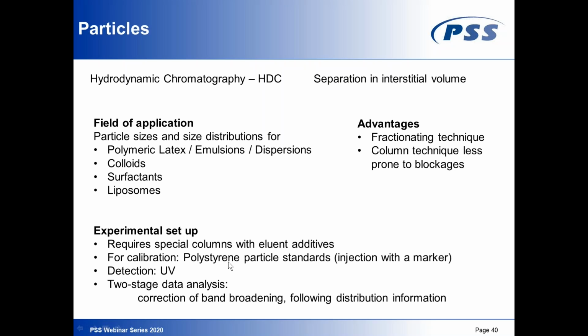For calibration, we use polystyrene particle standards instead of the molecular weight standards. Important is that we inject them together with a marker so that we can have a very reproducible elution. Detection would be UV because we use polystyrene particle standards here. And the data analysis itself would then be a two-stage data analysis. First of all, we need a correction of band broadening, and then we need to get our distribution information. And for both of these, the calibration with the polystyrene particle standards is used.